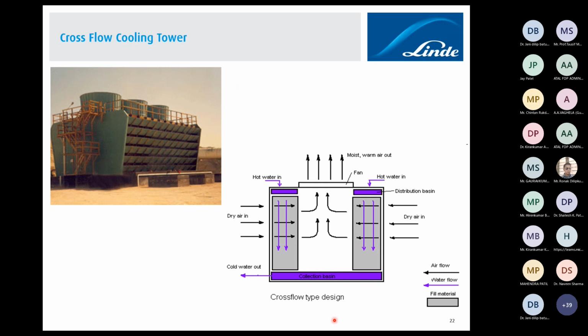So how does it work? Look at the working principle. Fill material is there on both sides, and in the center you will find a completely hollow portion. Dry air from the louvers will go inside, and by virtue of the fan moving, the air will go upward, and on both sides you will find water. Water is being spread over the cooling tower fill material, and this is how air and water heat exchange takes place. You can see the blue arrow is air and black is water, so you can say perpendicular movement is happening, and this is how cooling takes place.